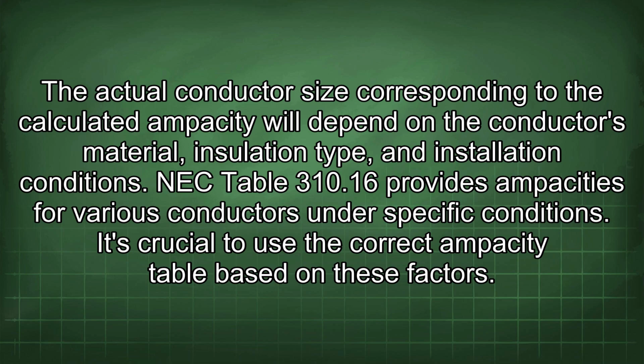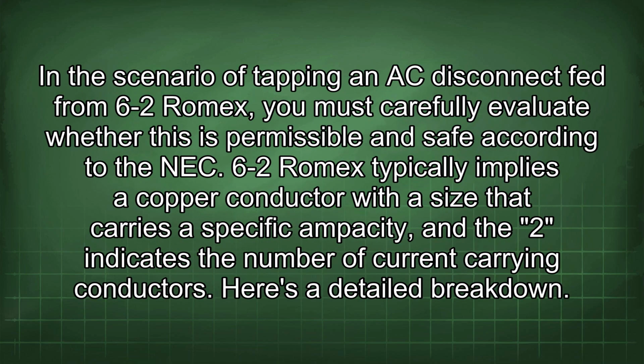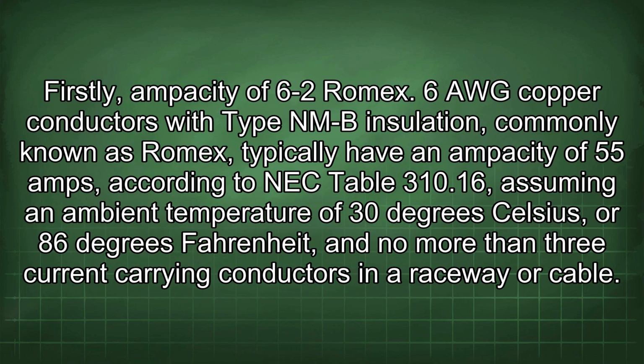It's crucial to use the correct ampacity table based on these factors. In the scenario of tapping an AC disconnect fed from 6-2 Romex, you must carefully evaluate whether this is permissible and safe according to the NEC. 6-2 Romex typically implies a copper conductor with a size that carries a specific ampacity, and the 2 indicates the number of current carrying conductors. Here's a detailed breakdown. Firstly, ampacity of 6-2 Romex.